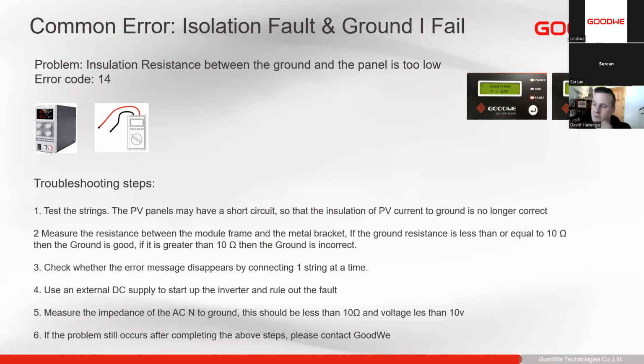So for that, we can always just measure with a multimeter and make sure that our grounding is correct. Maybe there's a loose connection somewhere in the ground or the neutrals, and we need to make sure that that is well bonded. Then the isolation fault is going to be on the module side. So for that, one of the quickest things to do is disconnect all your modules, test one string, see if the one string works, next string works, and then we can also test the MPPT. So find one string if it works, we test the other MPPT with that string, so if we have multiple MPPTs, we can test all the MPPTs with that one string, and if there's no isolation fault, then we can be sure everything is fine with the inverter.